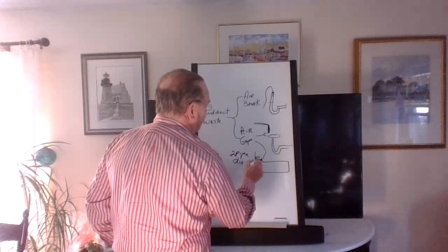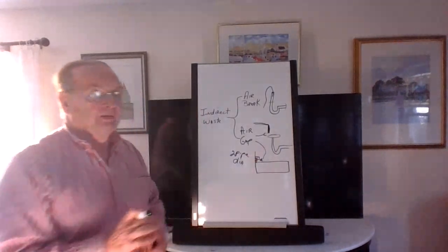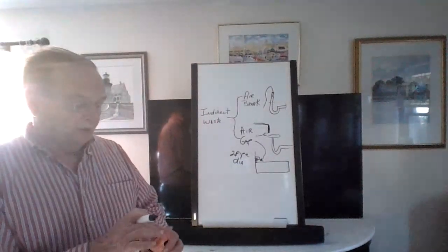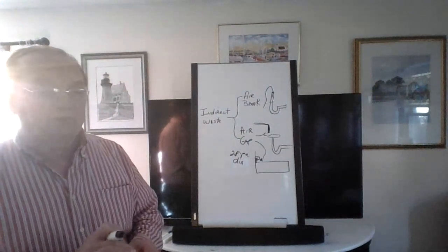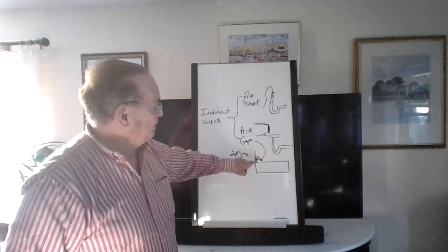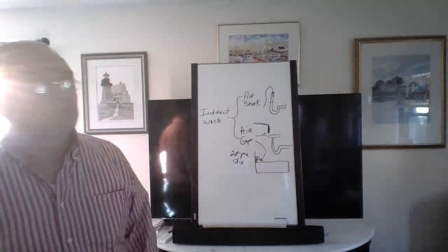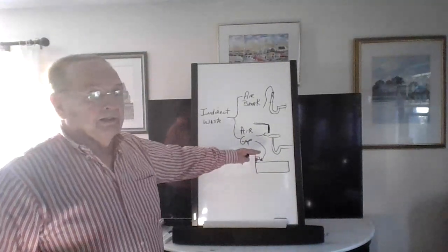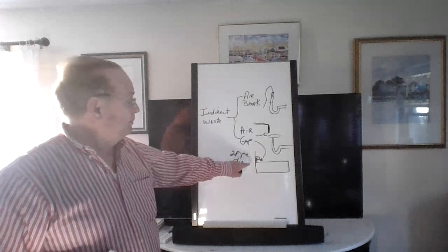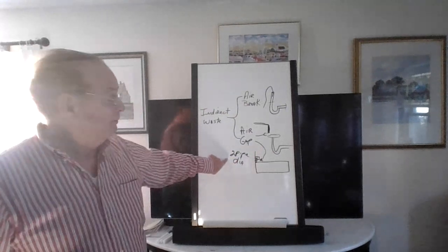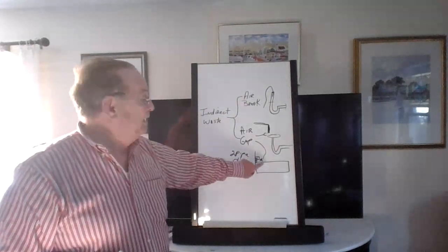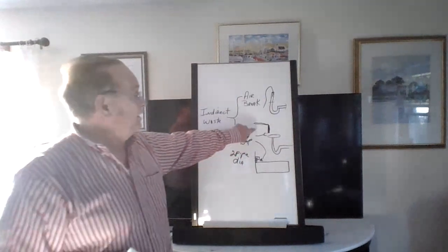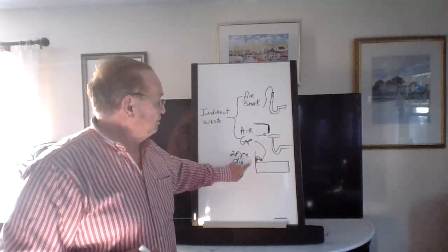So 1, 2. So whatever the spout, we'll say the spout is equivalent of 1.25 inch circle. This would have to be up 3 inches, which is probably, I think everybody here puts them up at least 3 inches high. Again, you all have your own way of doing it, but it's supposed to be a minimum of 2 pipe diameters above the flood level rim. That's an example of an air gap. This is drainage, these two. This one is actually pressure right here.